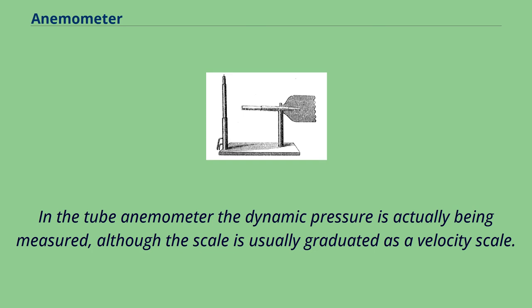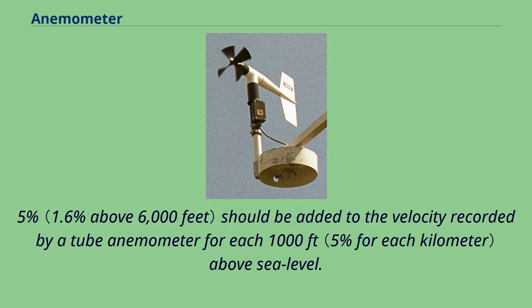In the tube anemometer the dynamic pressure is actually being measured, although the scale is usually graduated as a velocity scale. If the actual air density differs from the calibration value, due to differing temperature, elevation or barometric pressure, a correction is required to obtain the actual wind speed. Approximately 1.5% should be added to the velocity recorded by a tube anemometer for each 1000 feet above sea level.